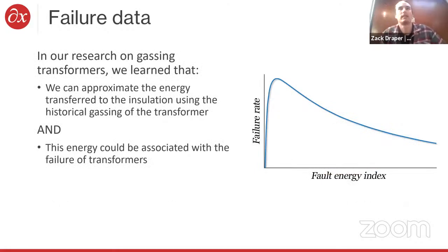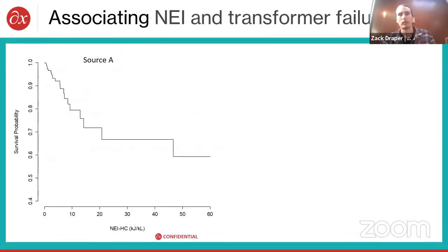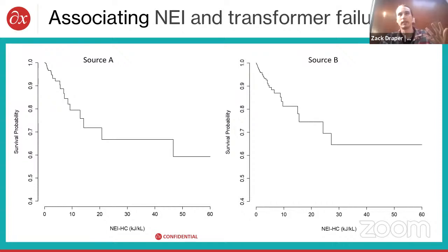So in our research on dissolved gas analysis, we simplified the gas data into the fault energy indices, tracking how much energy is being dumped into the insulation system, whether it's the oil or the paper. Then we used the historical trending of gassing to associate it with the failure data, so that we can understand in an objective way how gassing relates to failure. The way we did this is we took failure data from two different utilities, source A and source B. They have different fleets and different maintenance policies.